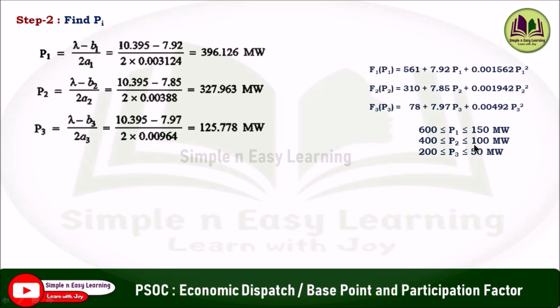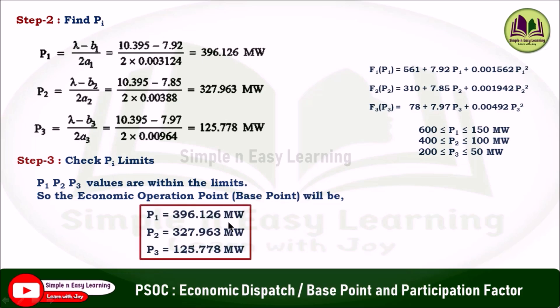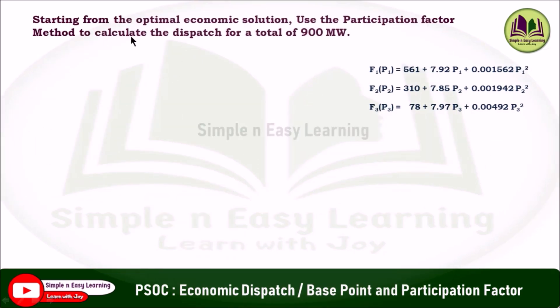Step 3: Check Pi against limits. P1 limits are 150 to 600 — P1 = 396.126 MW, within limits. P2 limits are 100 to 400 — P2 = 327.963 MW, within limits. P3 also lies within its limits. So the economic operating point (base point) is: P1 = 396.126 MW, P2 = 327.963 MW, P3 = 125.778 MW.